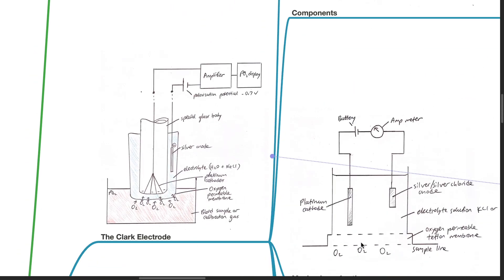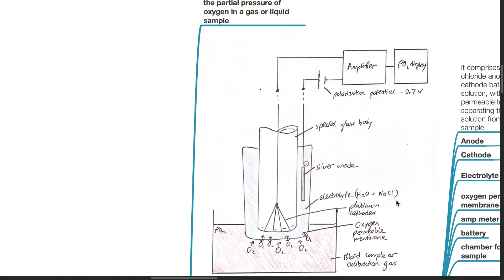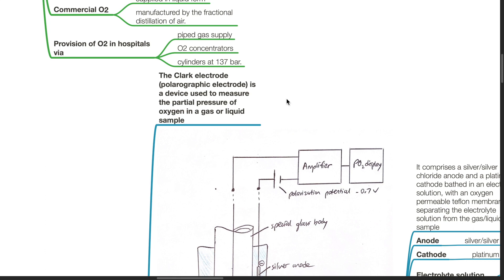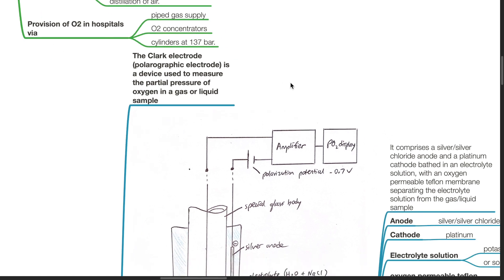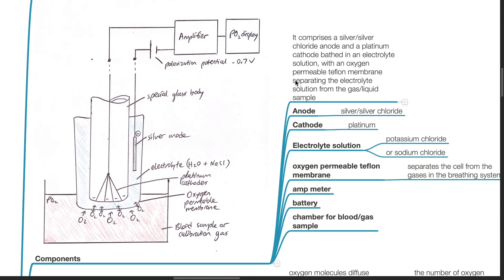The Clark electrode, or polarographic electrode, is a device used to measure the partial pressure of oxygen in a gas or liquid sample. Its components include a silver-silver chloride anode and a platinum cathode, bathed in an electrolyte solution, with an oxygen-permeable Teflon membrane separating the electrolyte solution from the gas or liquid sample.